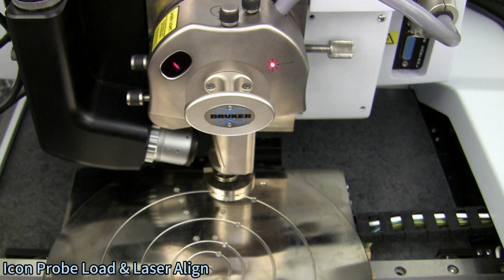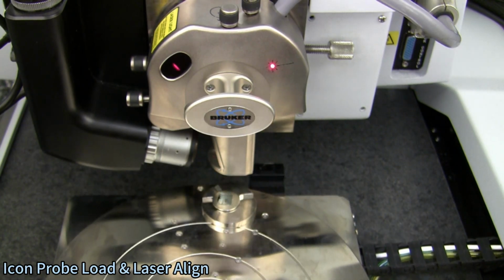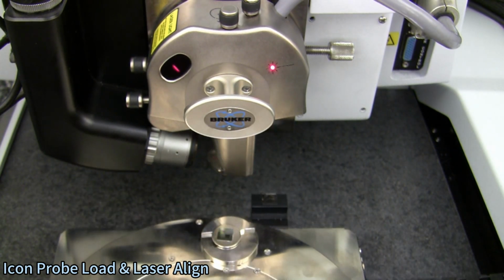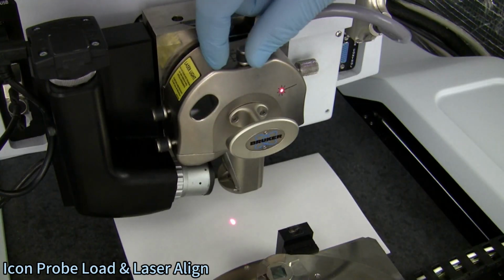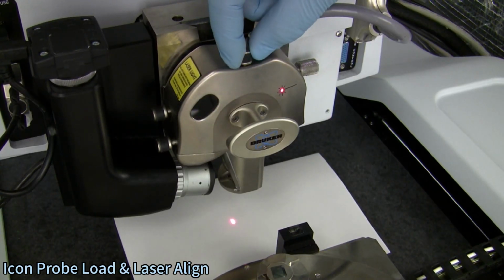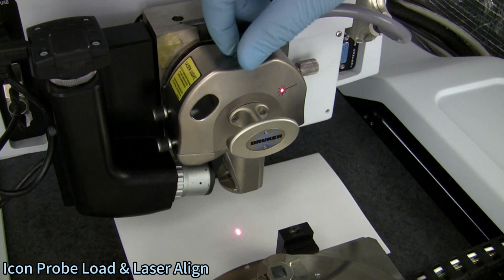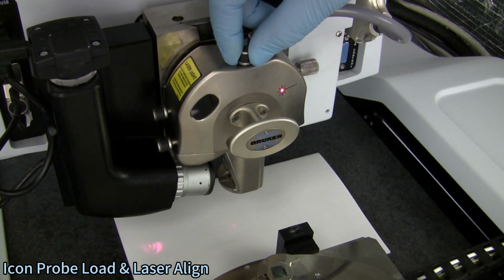Move the stage forward to allow room for the projected laser beam. Use a sheet of paper or any suitable surface to observe the projected laser spot. Align the laser onto the probe by rotating the positioning knobs until the beam is interrupted by the cantilever arm, creating a shadow.